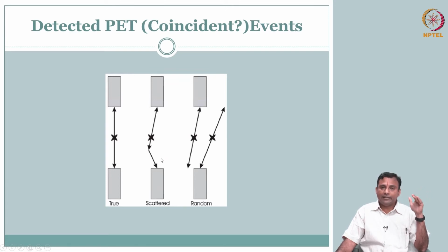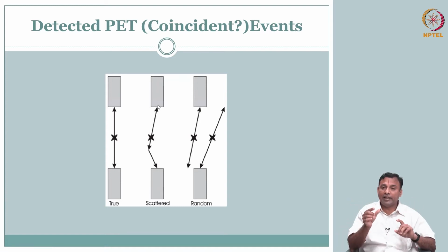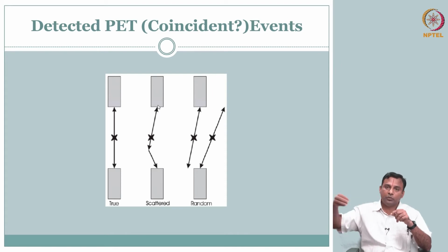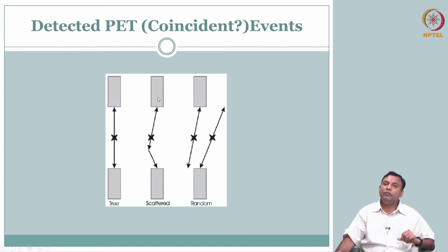if it is scattered, the energy is reduced. So at least the scattering that is happening within the crystal after it comes to the crystal, we can reduce. How does this happen? From the body is one story. The other part that we saw when we covered the Anger camera is your crystal thickness, right. You want the efficiency to improve, so if you increase the thickness, what is going to happen? You are going to have Compton scattering from the crystal before it goes into the photomultiplier tube and gets amplified. So at least that we should be able to reduce.